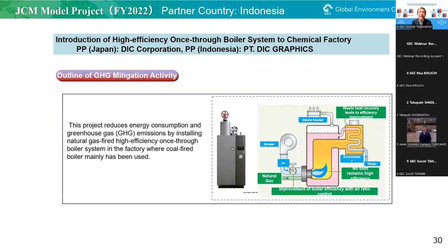This project reduces energy consumption and carbon dioxide emissions by installing a natural gas-fired high-efficiency once-through boiler in a factory where coal-fired boilers have mainly been used, so this equipment replaces such coal-fired boilers. The once-through boiler can save energy greatly, with energy efficiency of almost 100%, and the operating system for the boilers can control the appropriate number of machines according to varying demand. This type of boiler is now popular in Japan. We hope this project contributes to the diffusion of this technology in factories in Indonesia.